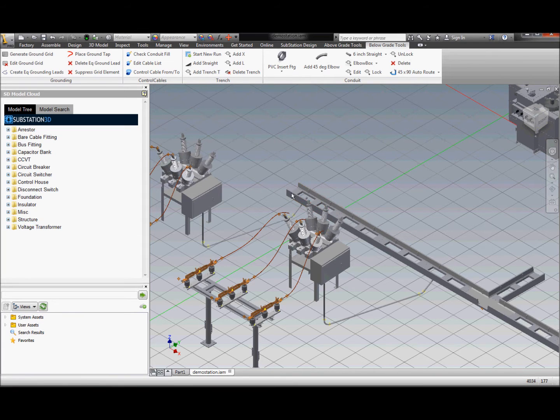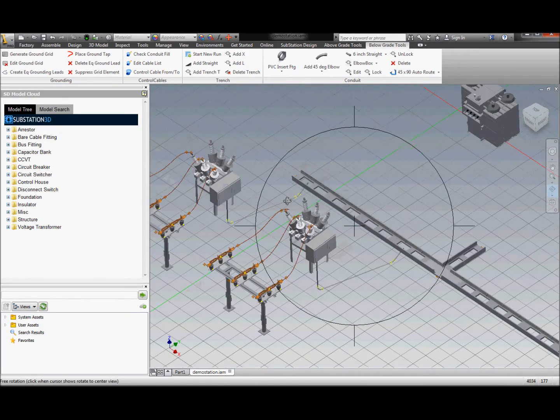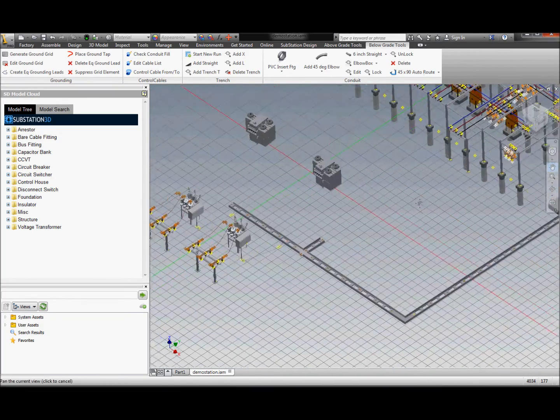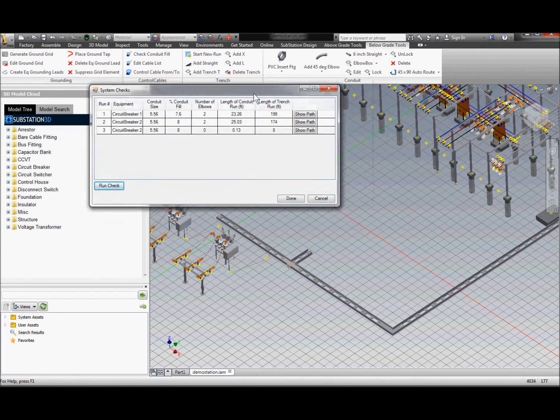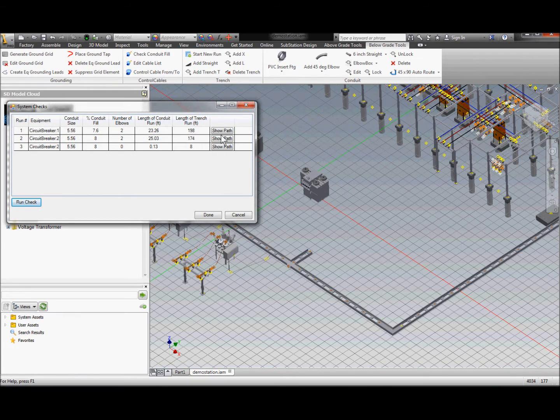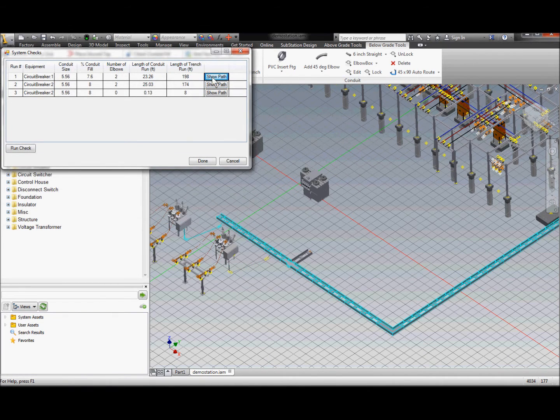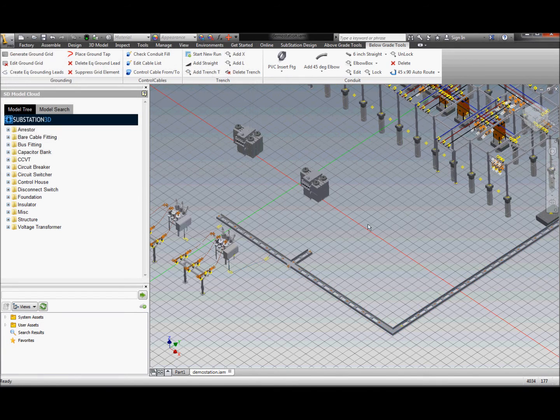Now that we've got a conduit run and a trench set up, let's take a look at some of the intelligence embedded in these components. We can do a system check and get a total length — a from-to directly from the equipment down the conduit, up the trench to the house. We can check each path of the equipment as well as the percent of conduit fill. Because we know the electrical information of the equipment, where the control house is, and which trench components each conduit piece is touching, we get a true from-to.